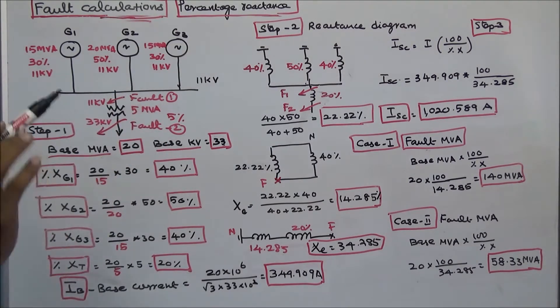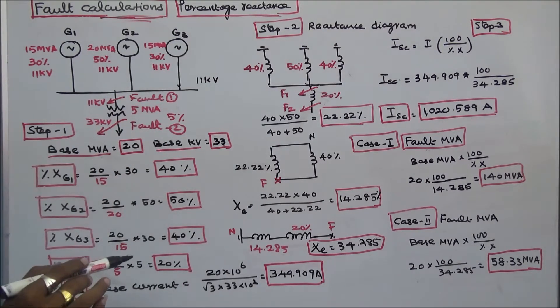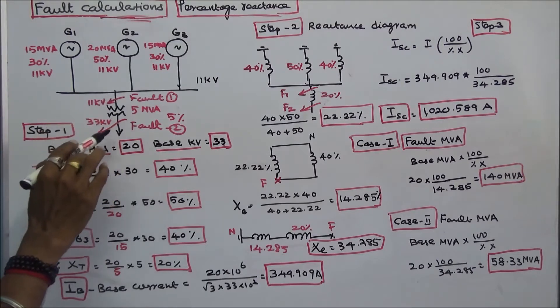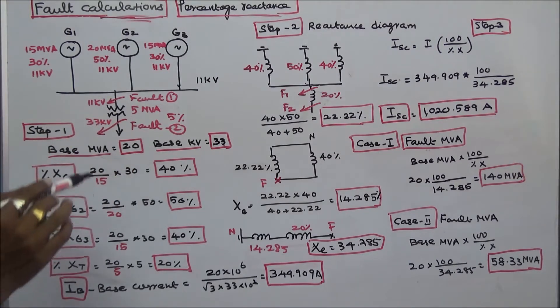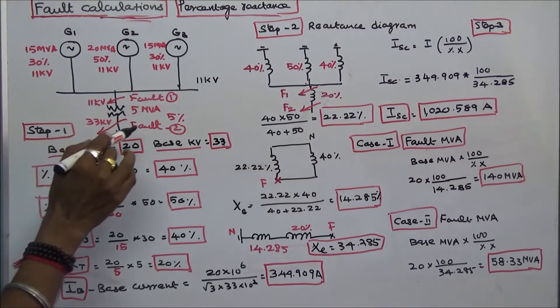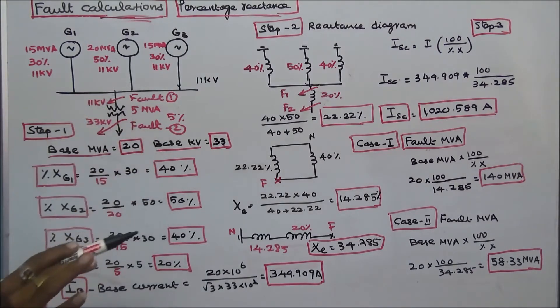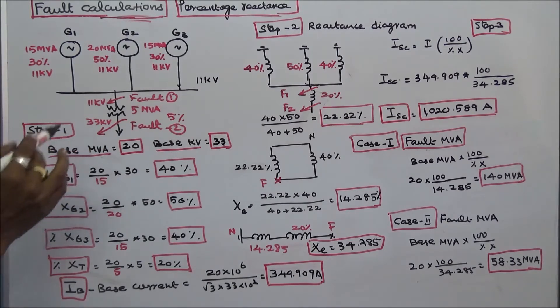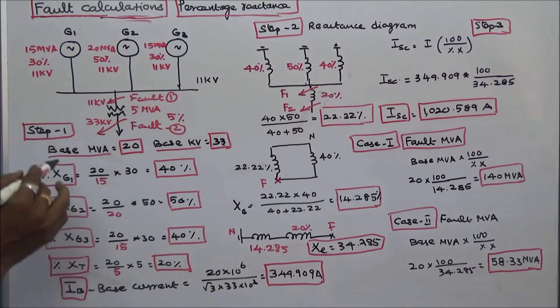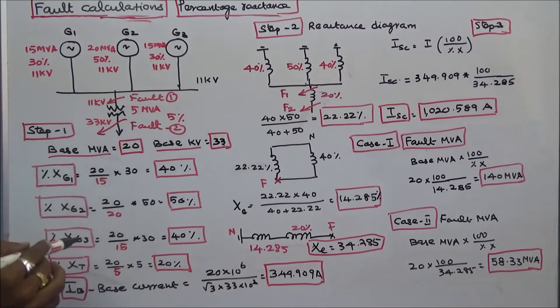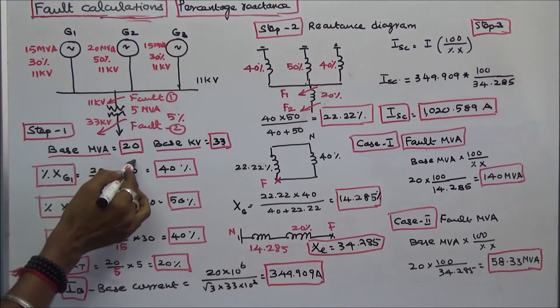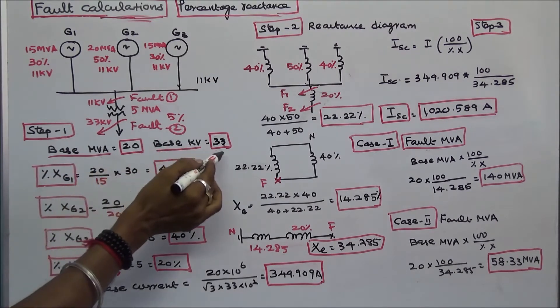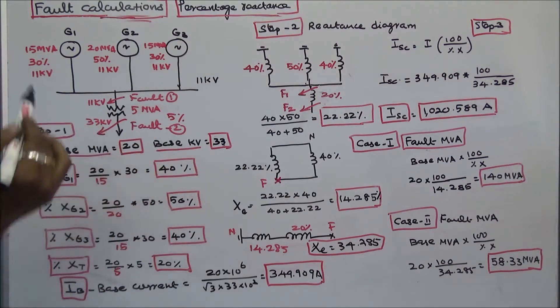Question number two: if a fault occurs at the high voltage side of the transformer, determine the fault MVA. Step one, we choose base MVA and base kV. Base MVA is equal to 20, and base kV is equal to 33.